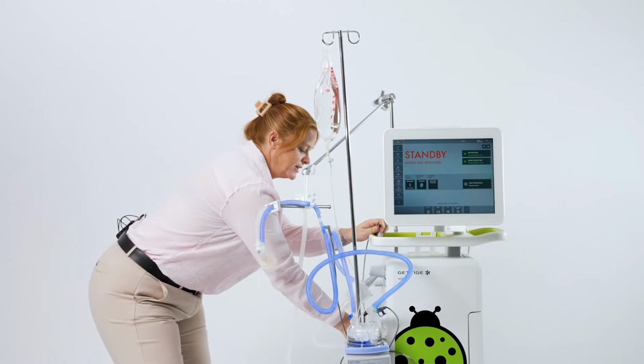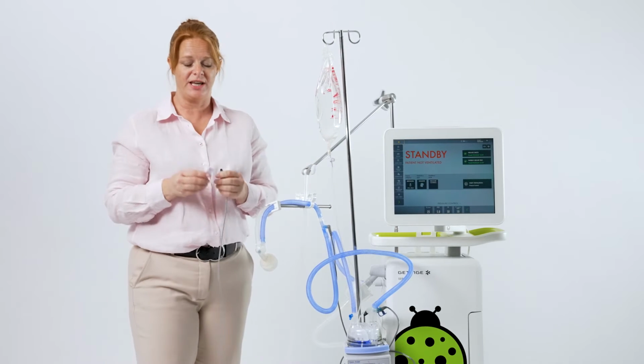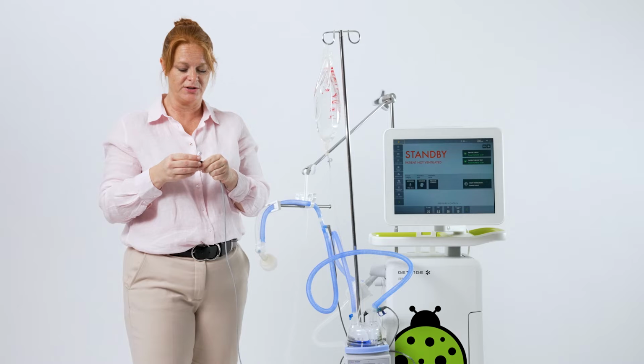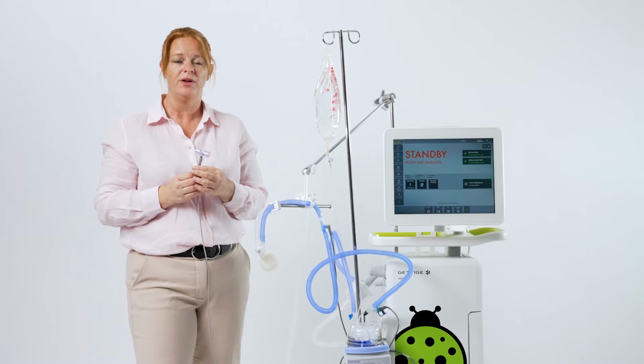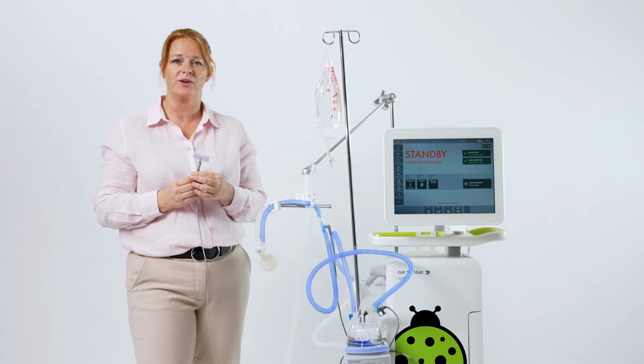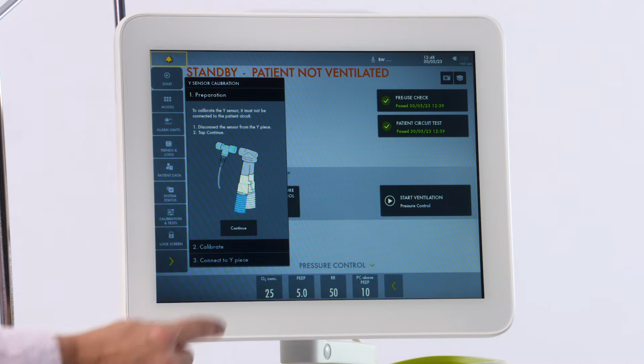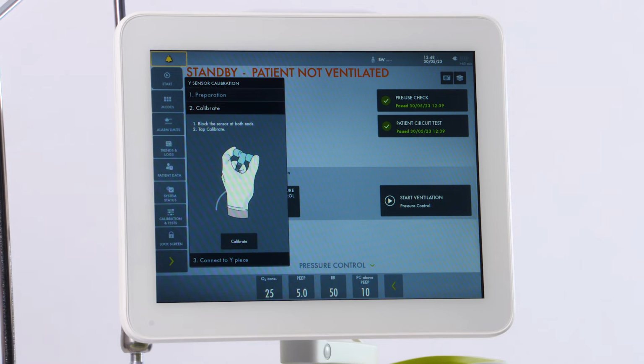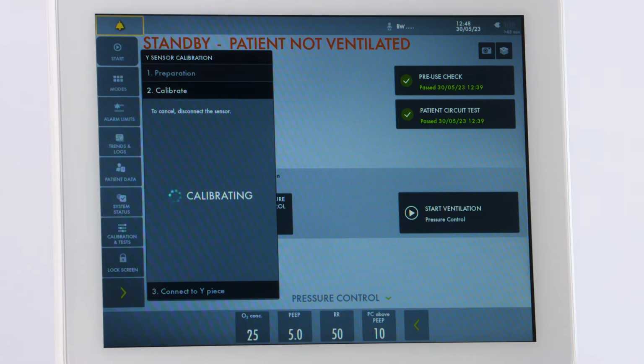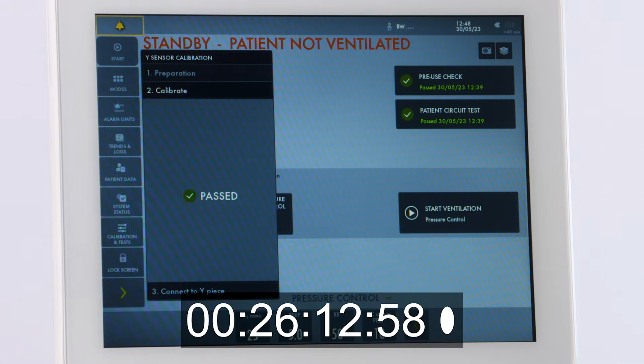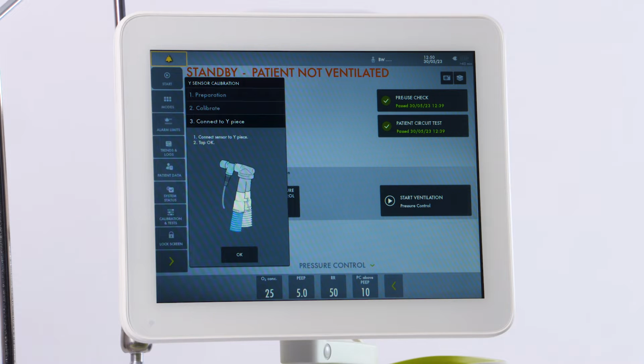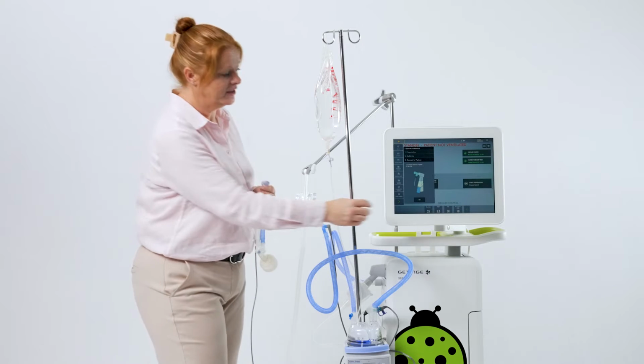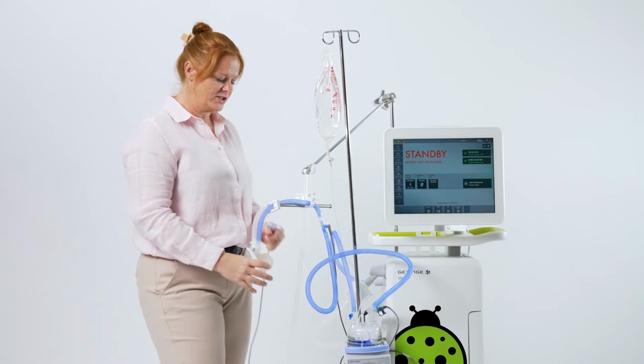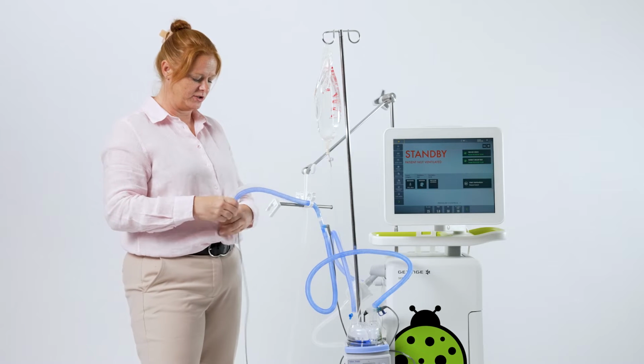Plug in the module into the side. Attach the cable and the flow sensor to the cable. You will then be directed by on-screen tutorials, as this needs to be done before using. Block the Y and press calibrate. Touch OK and then you're ready to start. Attach your flow sensor to your circuit.